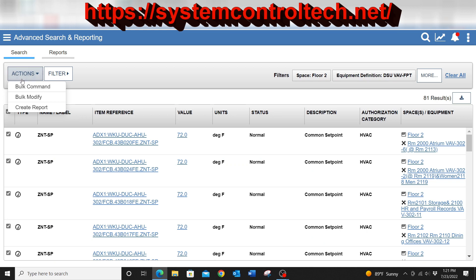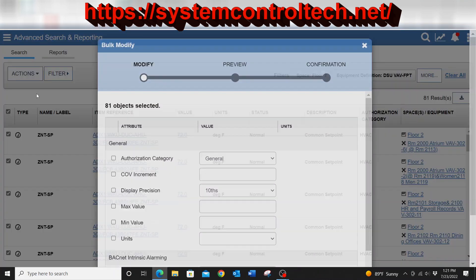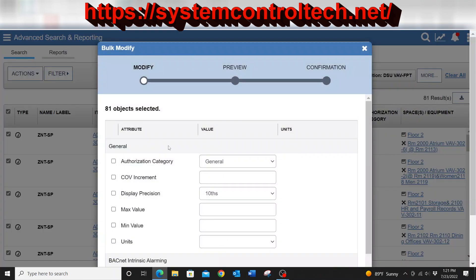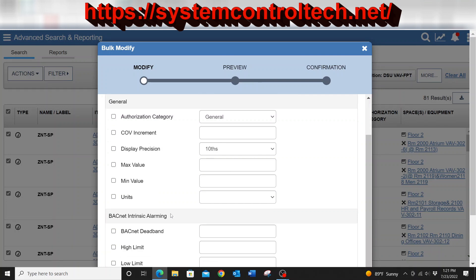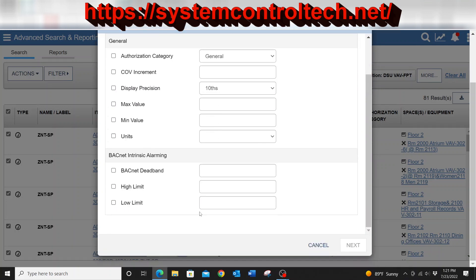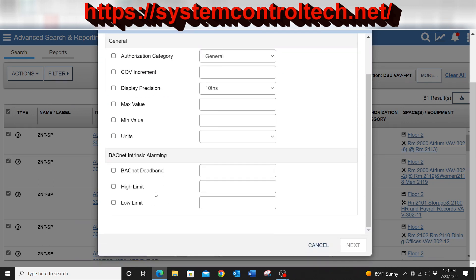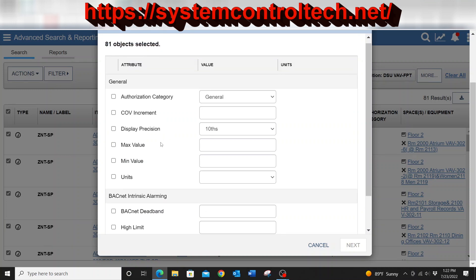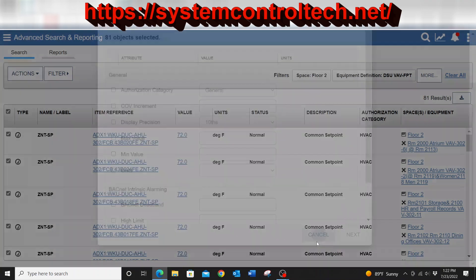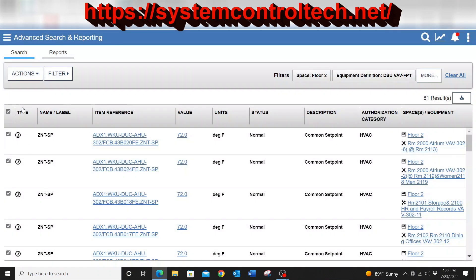You also noticed from this action tab, I have the option of creating, doing a bulk modify. I can actually select that. And there's a lot of things that I can do. I can change the authorization category here, change of value, increment, display precision, min, max values. There's a lot of things that you can do from this bulk command option, and it can save you a lot of time in your system. Instead of having to go in there and change everything just one step at a time, you can change it right here in the bulk modify.